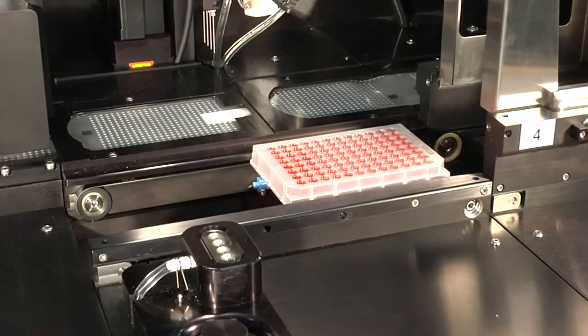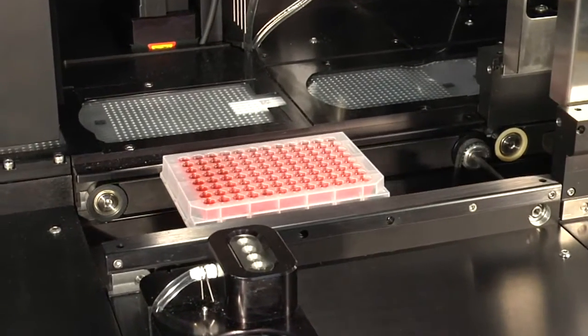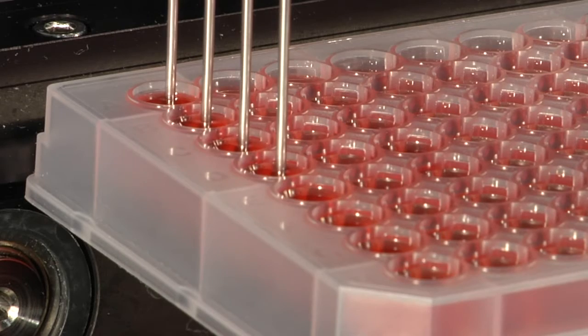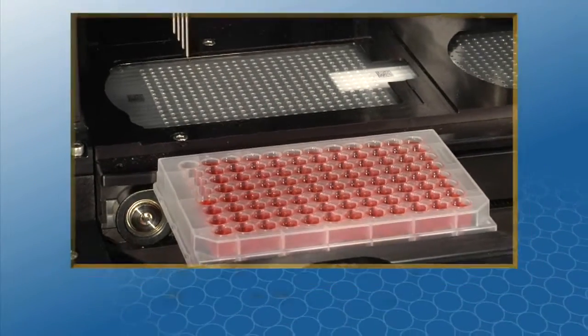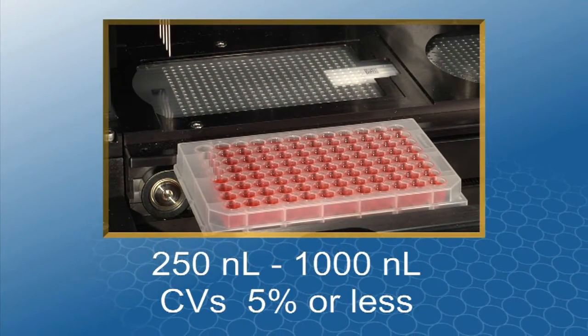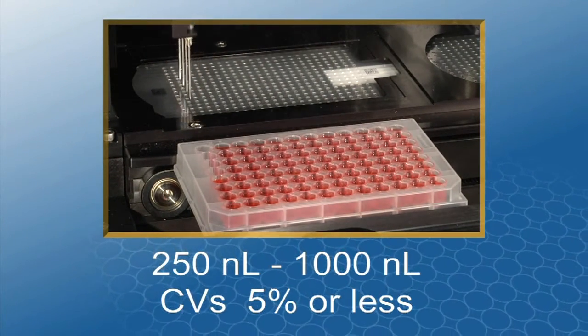The array tape is automatically advanced to the non-contact dispense jet which accurately adds the master mix to the samples already in the wells in 30 seconds. Dispense volumes range from 250 to 1000 nanoliters with CVs of 5% or less.